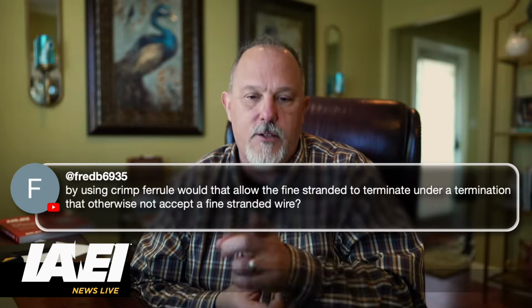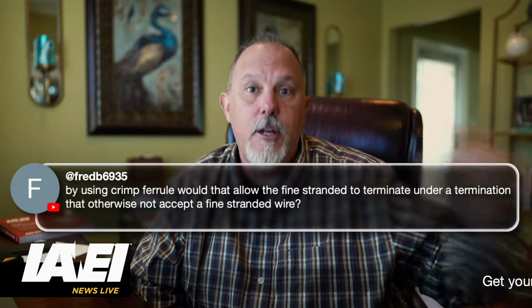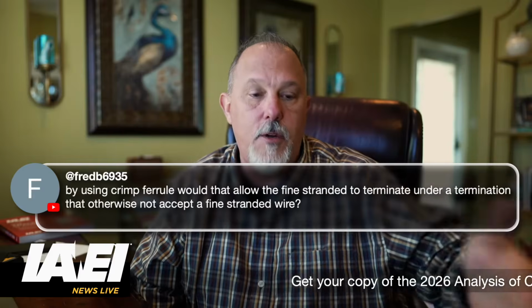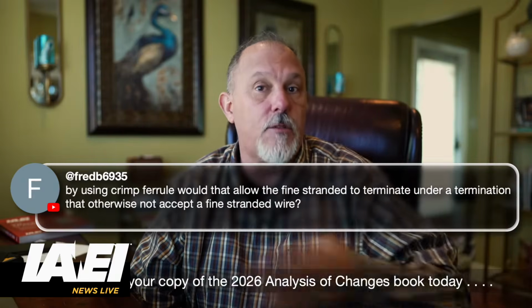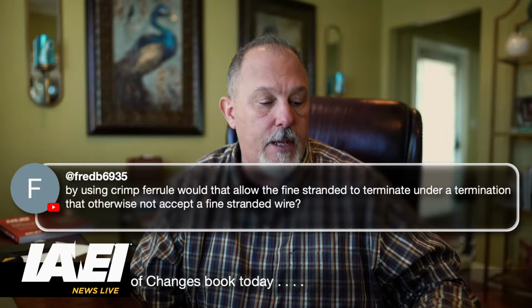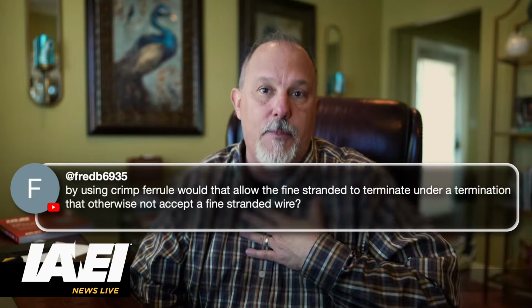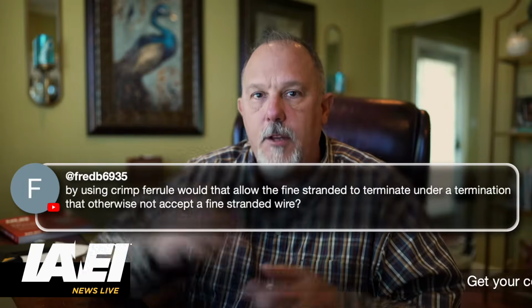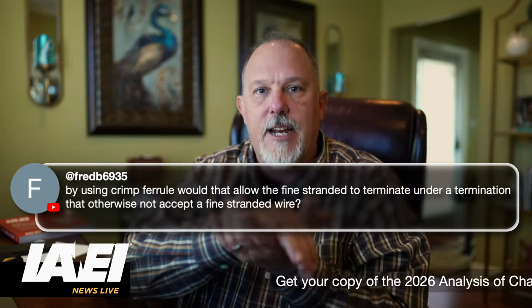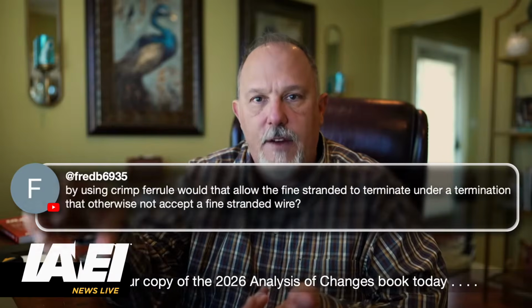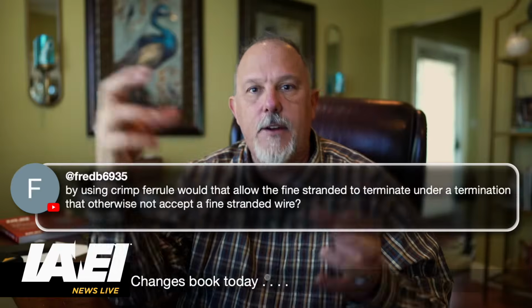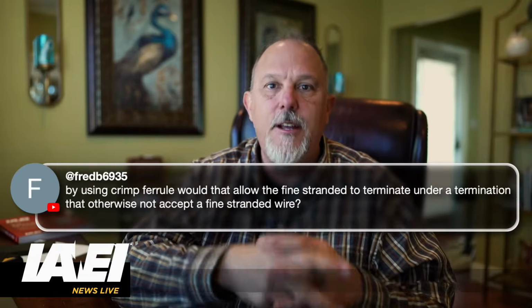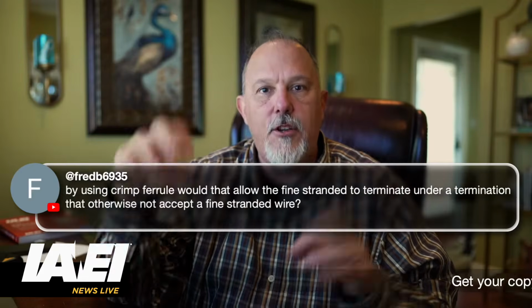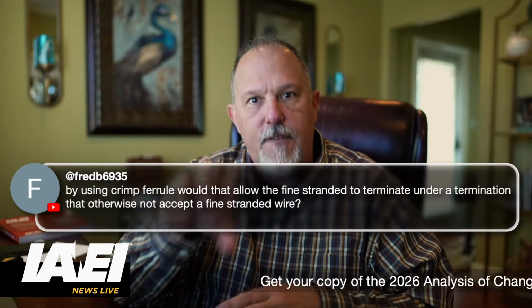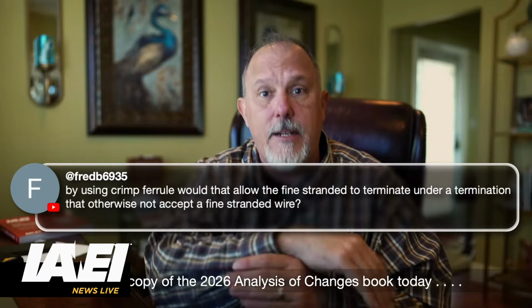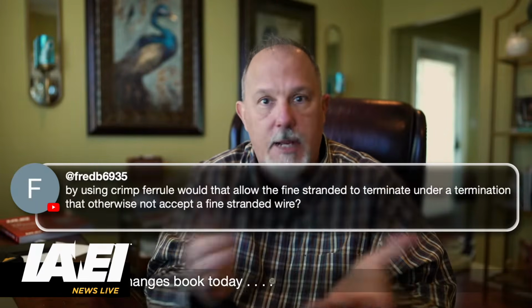My weasel words to answer that question is look at the listing. Talk to the manufacturer. I could not tell you what each manufacturer permits or doesn't permit. It would be a good guess in my book to say you're in the right ballpark where you fit those fine stranded conductors inside of a ferrule, as long as that ferrule is listed for fine stranded. And then when you use that ferrule and place that on the circuit breaker termination, make sure that the circuit breaker is listed for that. So you've got two different areas. You've got the ferrule manufacturer, and the ferrule manufacturer may tell you they've tested it and listed it on circuit breakers and other types of terminations.